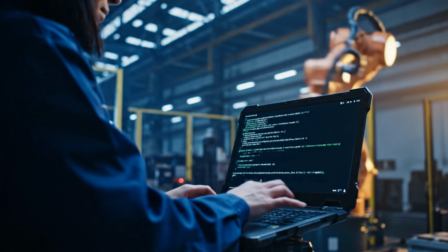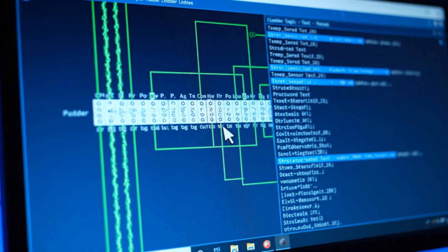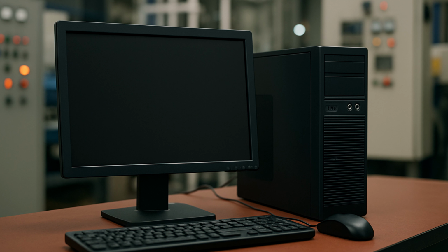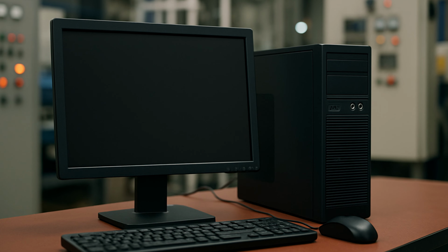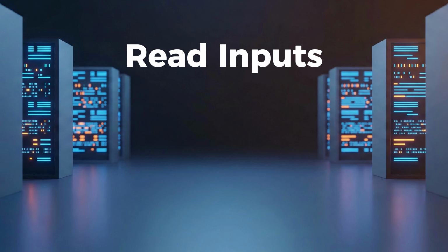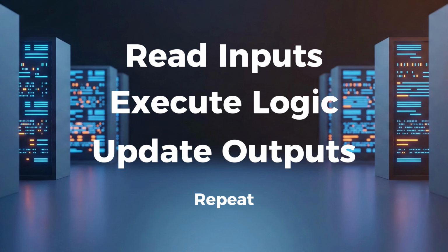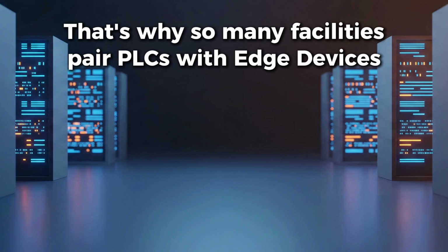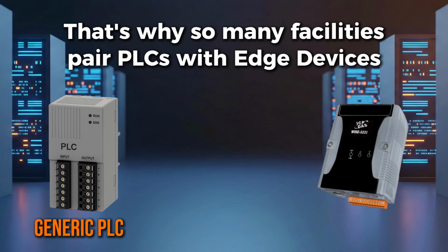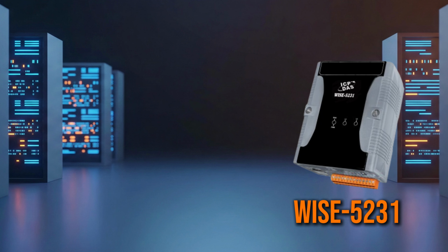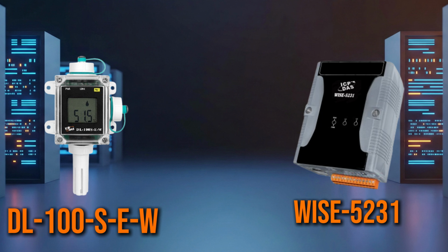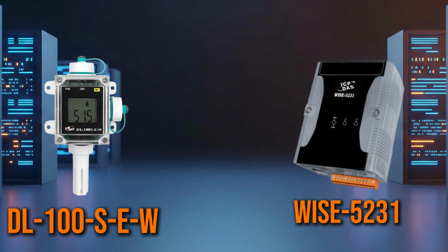And of course, there's the programming that brings all of this to life. PLCs use ladder logic, C, function block, and structured text, languages designed around real-time control. Unlike a PC, a PLC executes logic in a deterministic scan cycle. Read inputs, execute logic, update outputs, and repeat. That predictability is why so many facilities pair PLCs with reliable edge devices, such as WISE controllers for on-site logic processing, or DL series data loggers that maintain trend history even during network interruptions. All of this contributes to a system that stays stable, repeatable, and easy to maintain.